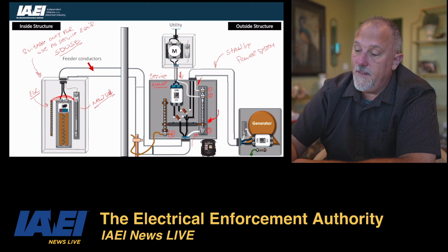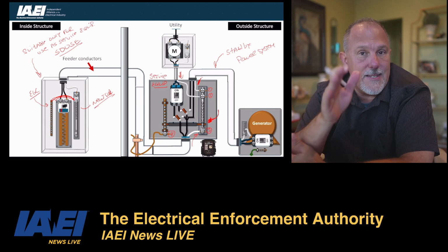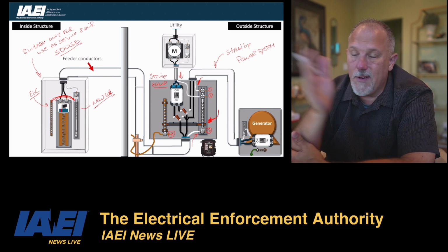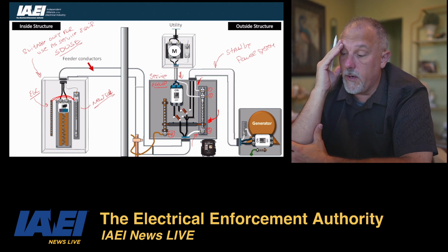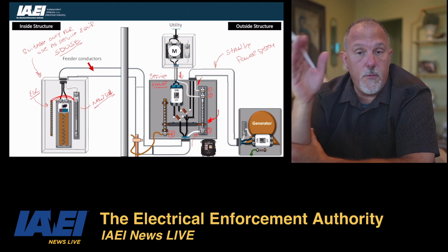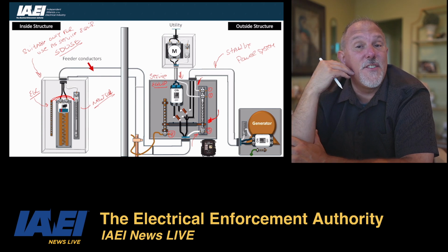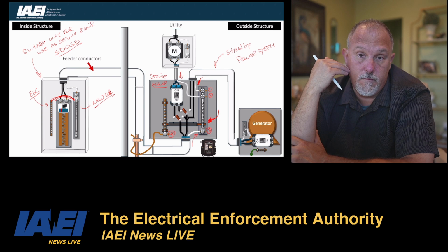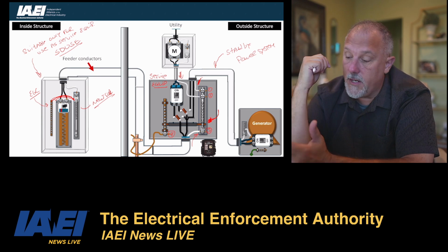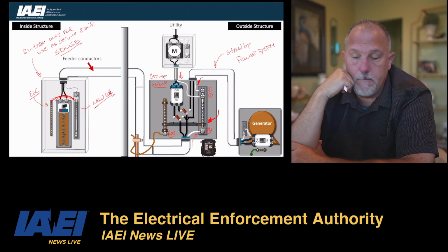Because if that existing panel board inside the house or outside the house, doesn't matter where it's at, if it's suitable only for use as service equipment, you're going to have to change the panel board out. If it can be converted, if you can undo the bond, then that's not a problem.